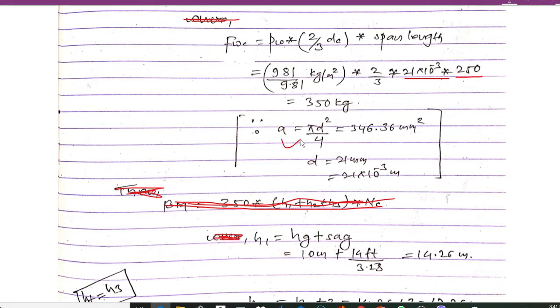The conductor diameter dc is obtained from the cross-section area using A = π d² / 4, where A = 346.36 mm². Solving gives d = 21 mm, i.e., 21 × 10⁻³ m. Substituting all values, we get Fwc = 350 kg for the 250-meter span.